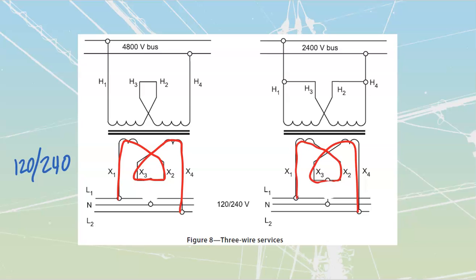The big difference between the one on the left and the one on the right is just how the primary side has been set up. I've got a 4800 volt bus versus a 2400 volt bus, but both are set up correctly, both generating full values of flux cutting through the core. This one's the low voltage, so it's connected in parallel. This one's the high voltage, so it's connected in series.